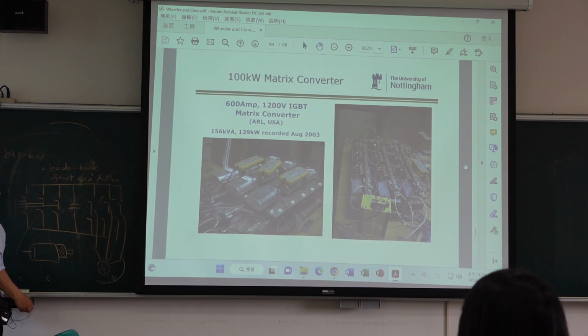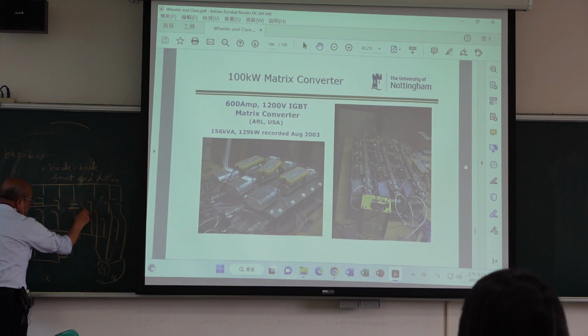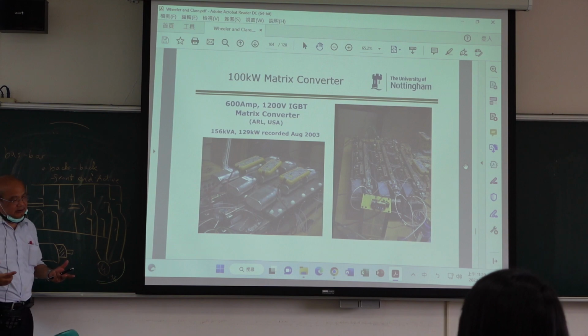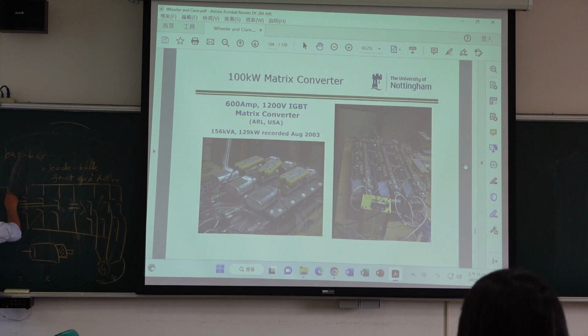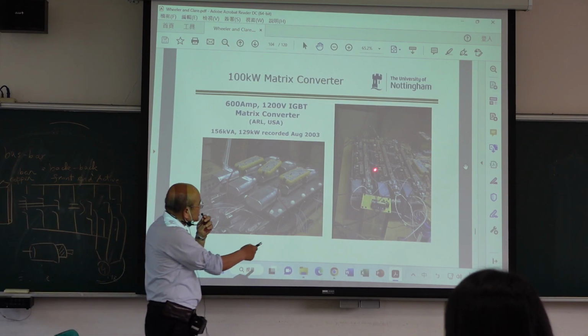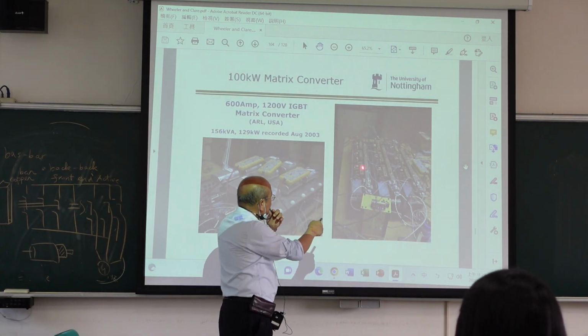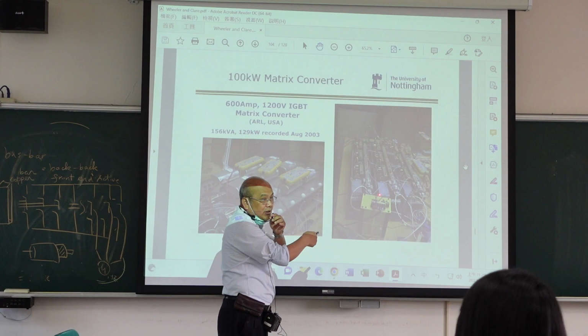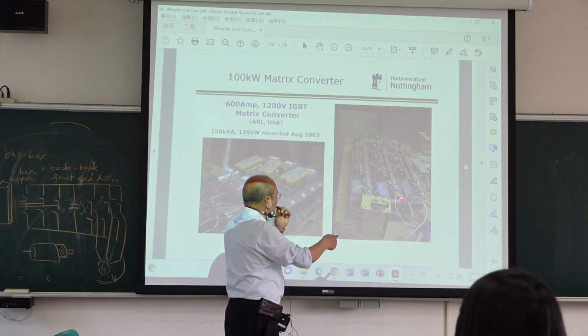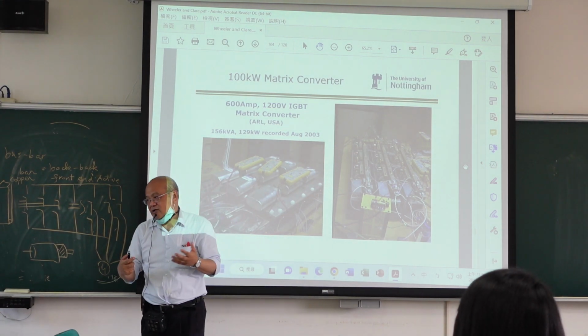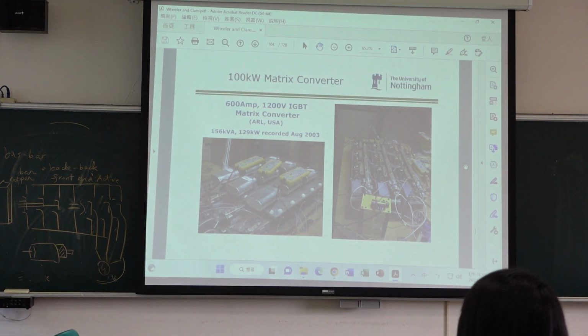What is a bus bar? Before, from here to here, you would use a wire. But a wire creates stray inductance, so you cannot use a wire here. You have to use a copper bar, a very thin copper bar, placed like this. So you can see this is the bus bar: no inductance, small resistance, so you can have a very good layout, no spikes, no snubber needed. This is the only way to do the layout.